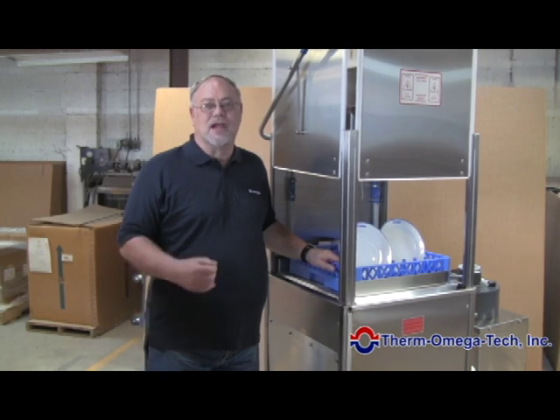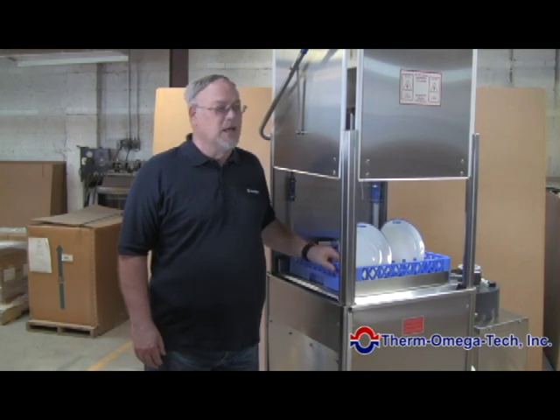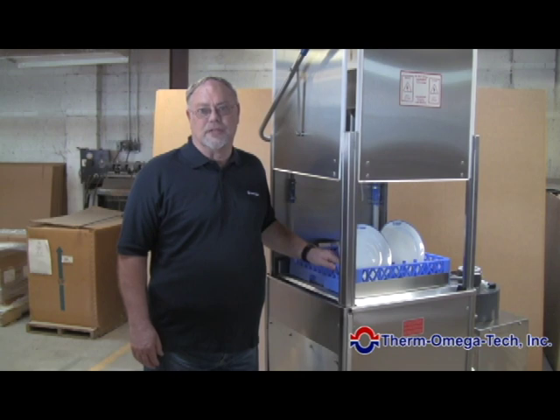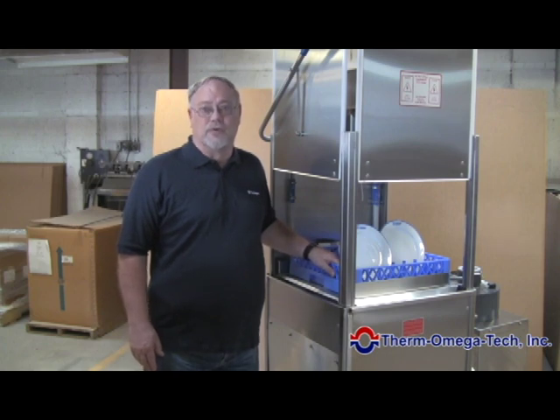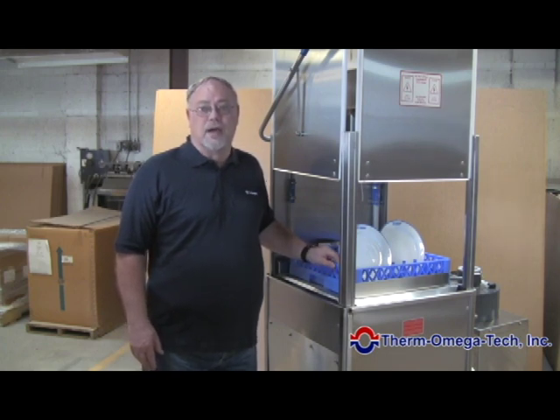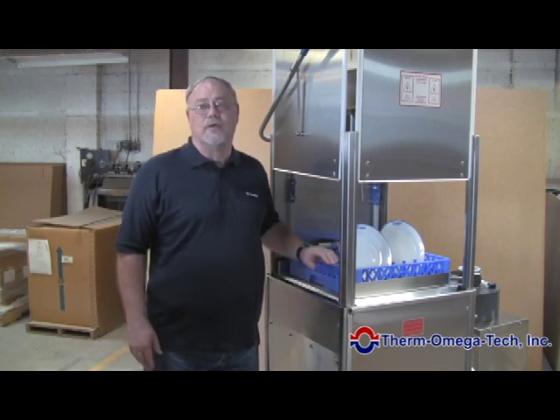This is our Commander 186, a commercial door-type dishwashing machine. It does basically one rack of dishes every 90 seconds. To accomplish that, we use a wash temperature of approximately 160 degrees and a final rinse temperature for sanitation of over 180 degrees. The combination of those two temperatures when emptying the water is now below the 140 degree requirement of most states for water going down the drain.